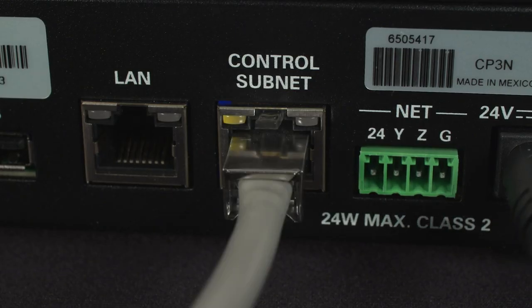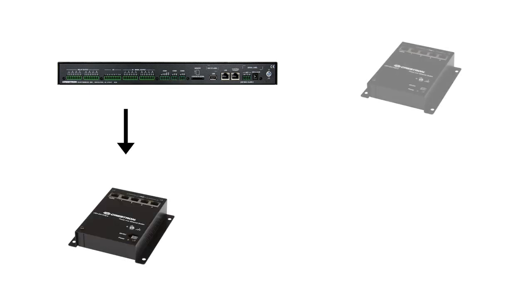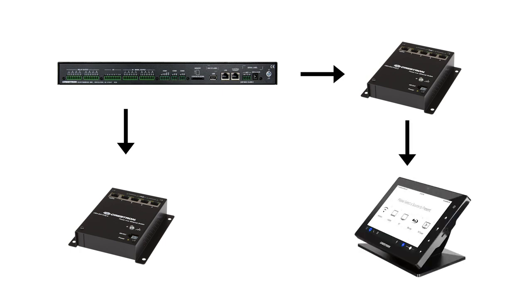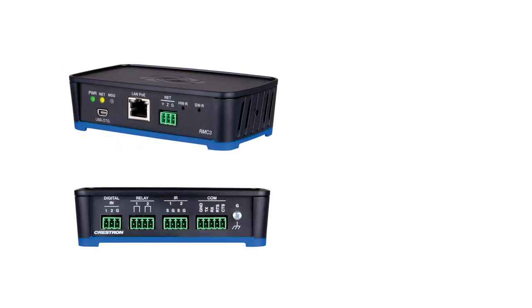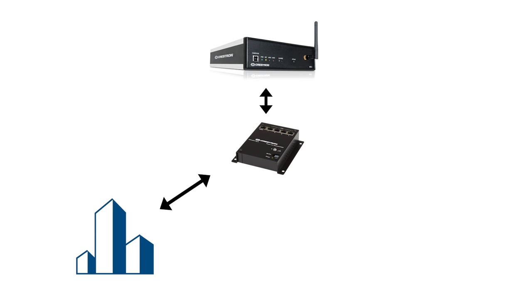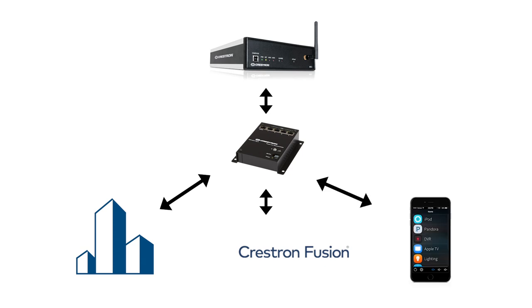All 3-series processors communicate via Ethernet on a standard Ethernet network. Ethernet is very important to the modern Crestron control system — many devices we communicate with use Ethernet, including other Crestron devices and many third-party devices. The 3-series processors support many Ethernet standards such as native BACnet (Building Automation Control Network), IPv6, and SNMP. Devices on Ethernet can be connected to building management and monitoring software such as Crestron Fusion, and Ethernet also allows control by mobile devices. Ethernet is so important that there is a whole other tutorial devoted to it.